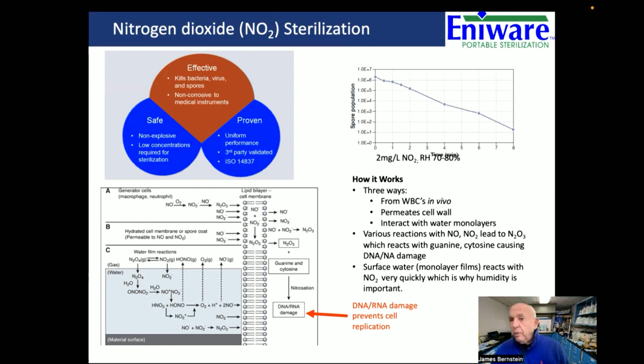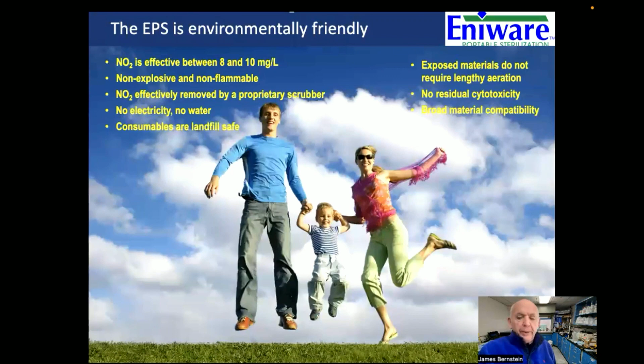The Eniware Portable Sterilizer is very environmentally friendly. It's effective in very low doses of NO2. It's non-explosive, non-flammable, unlike ethylene oxide. It can be rapidly removed by a very simple proprietary scrubber that's landfill safe. It uses no electricity or water. It has no residual cytotoxicity. It has broad material compatibility.